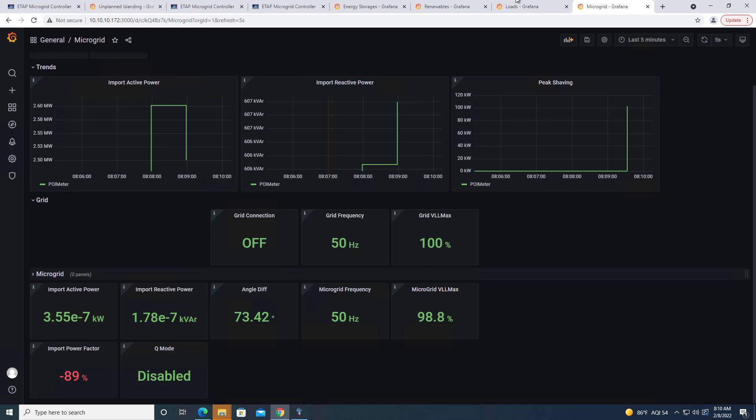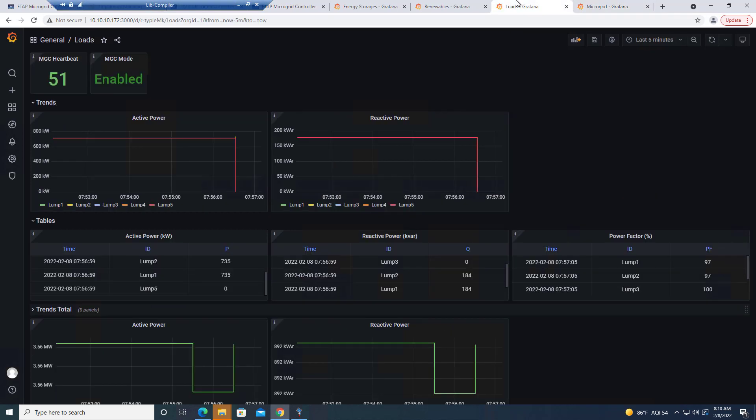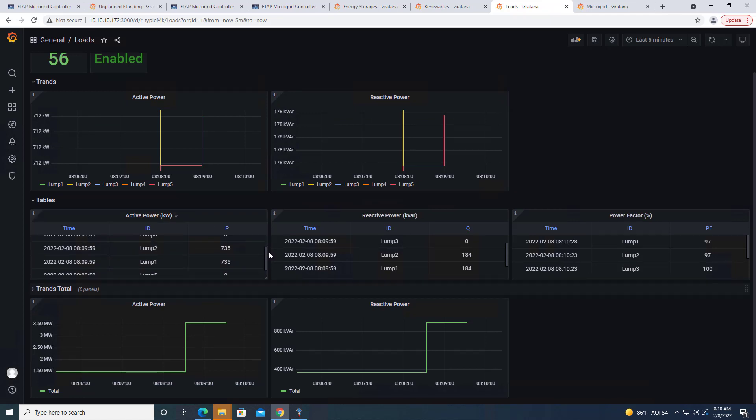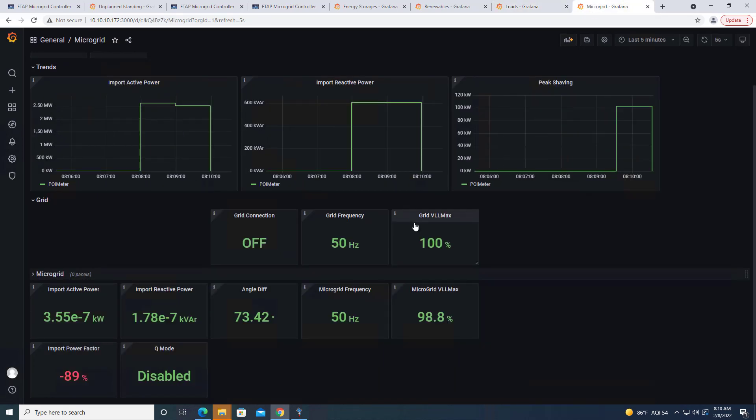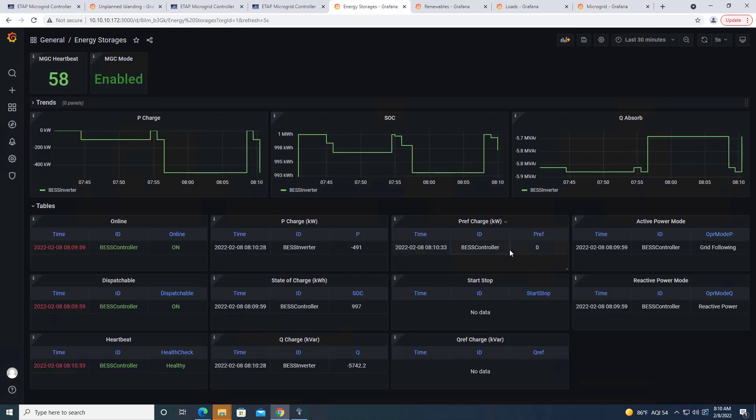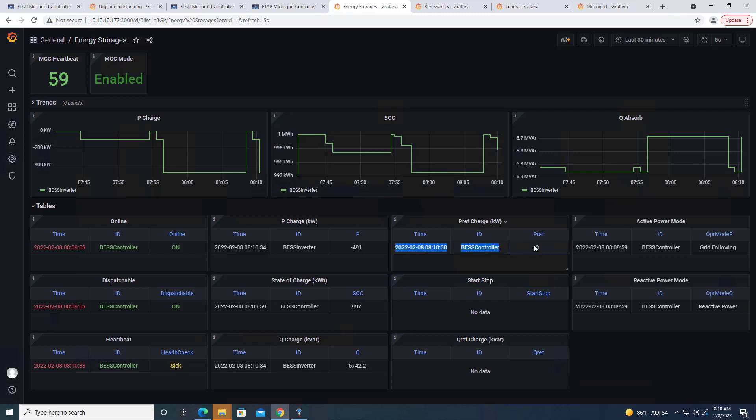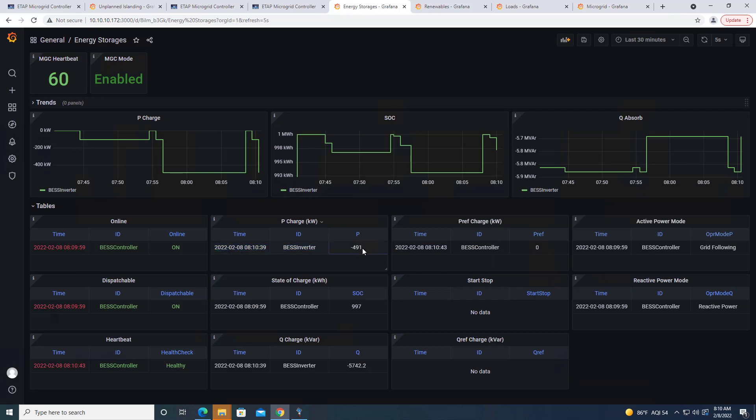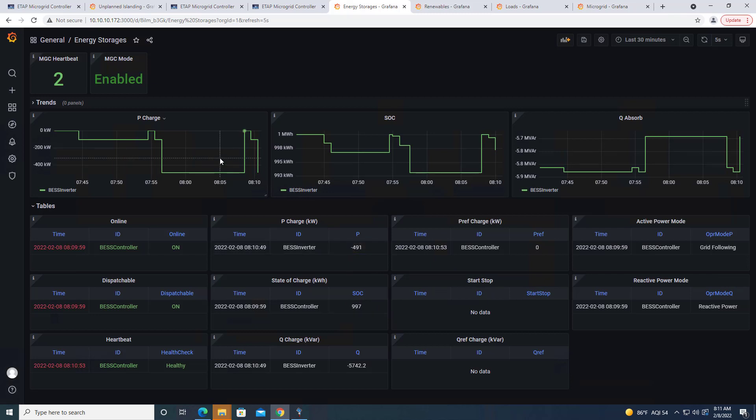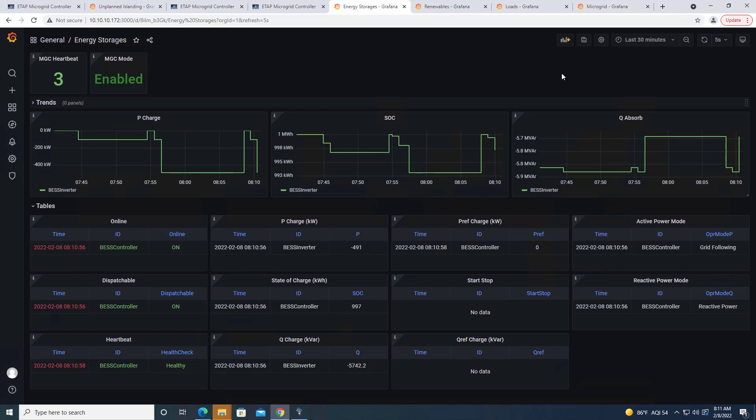Now let's go and take a look at the load. Look at here. I have three loads that they lost power. Only two loads have power. So we have done a successful load shedding here. Microgrid is in islanded mode, and we can look at what's happening with energy storage. We are not sending any more command to the battery. Battery is in grid forming, and the power gets determined by the system voltage and frequency. No more command, and SoC is going to drop. At this point, we are exporting power, so SoC is going to go down.